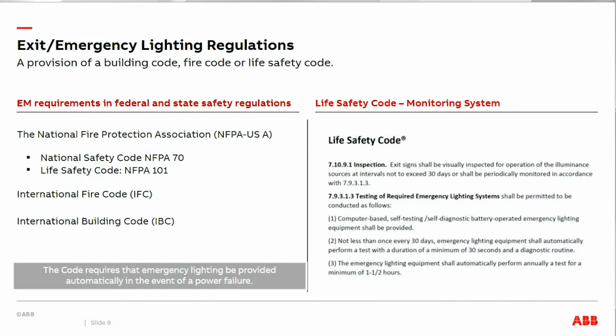Let's briefly visit code compliance in the U.S. for non-residential buildings. As stated in our scenario, exit signs and emergency lighting units must be tested every 30 days for 30 seconds, and once a year for a full discharge test of 90 minutes. The results of these tests must be recorded and be reproducible for compliance verification to the authority having jurisdiction. As the slide shows, computer-based testing is allowable by code.